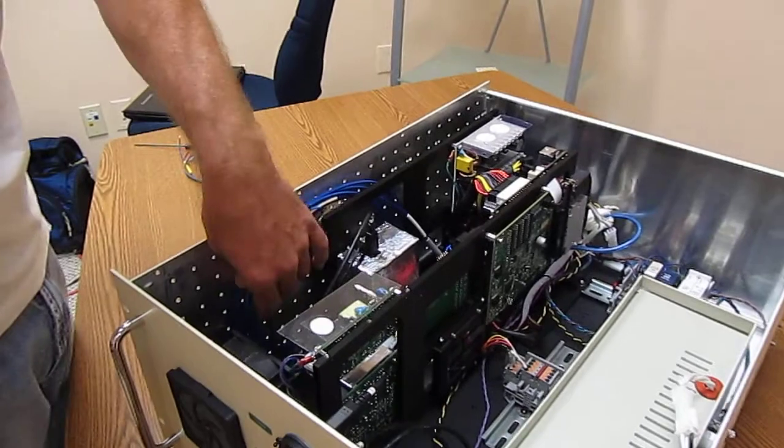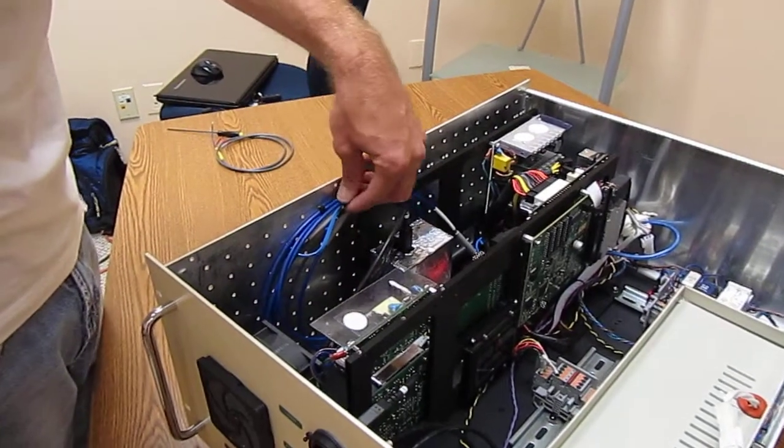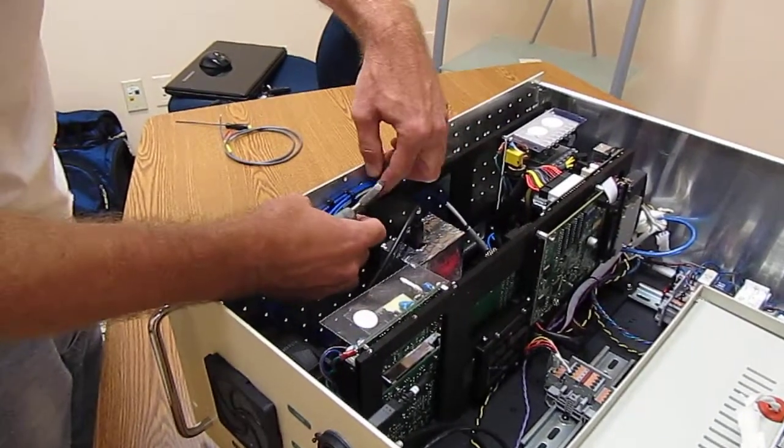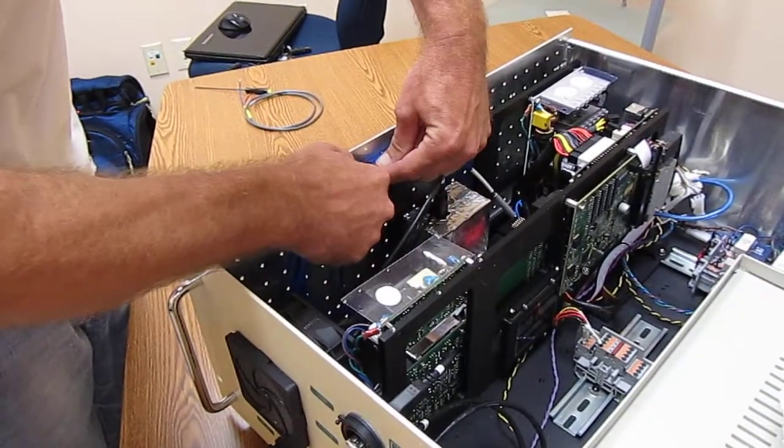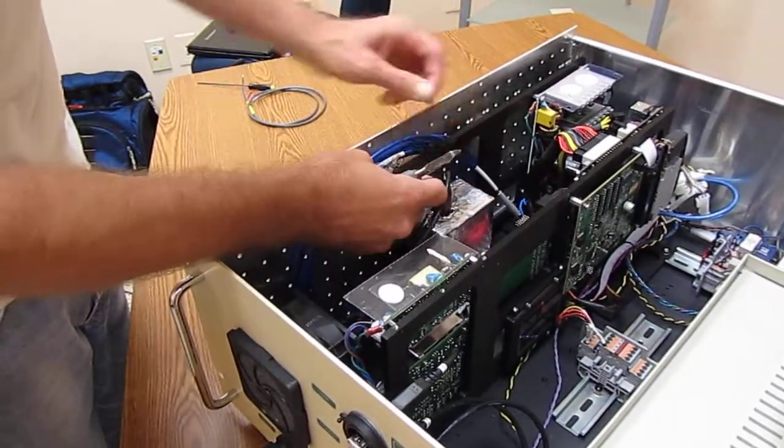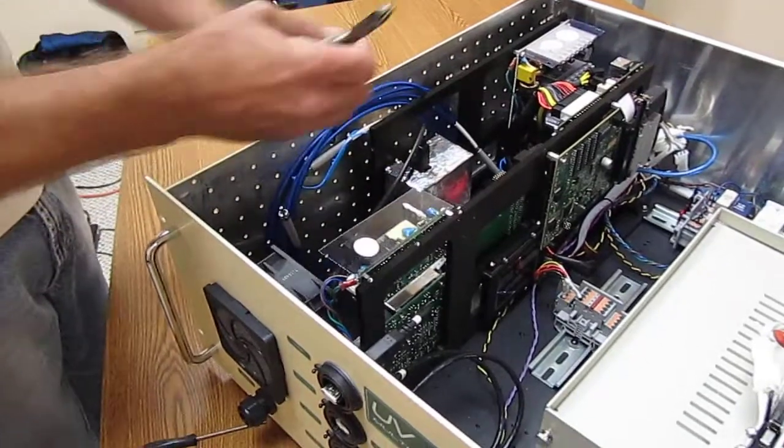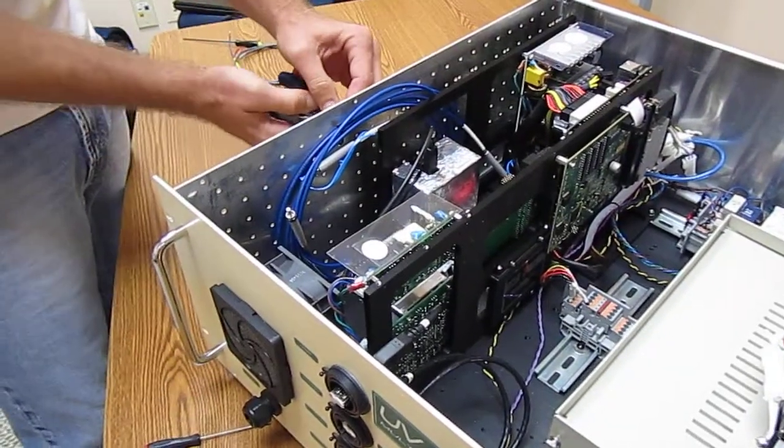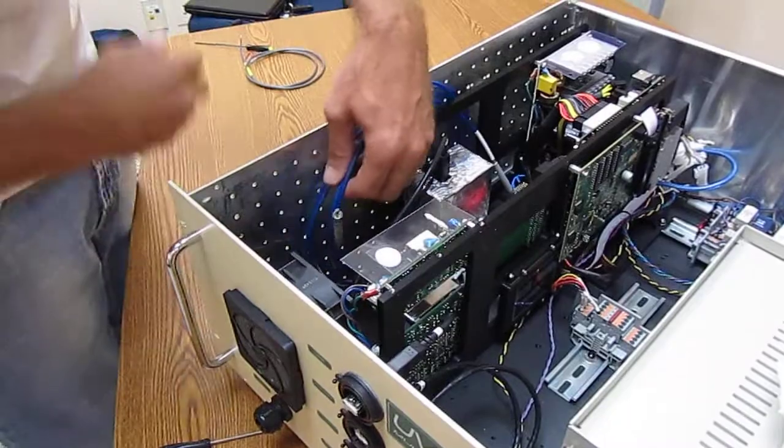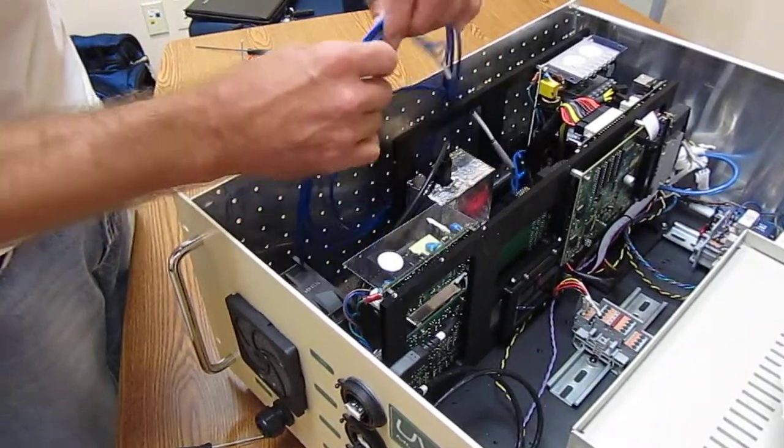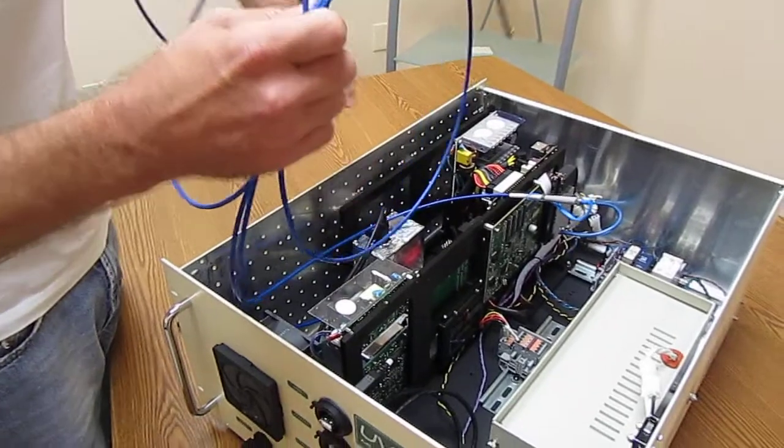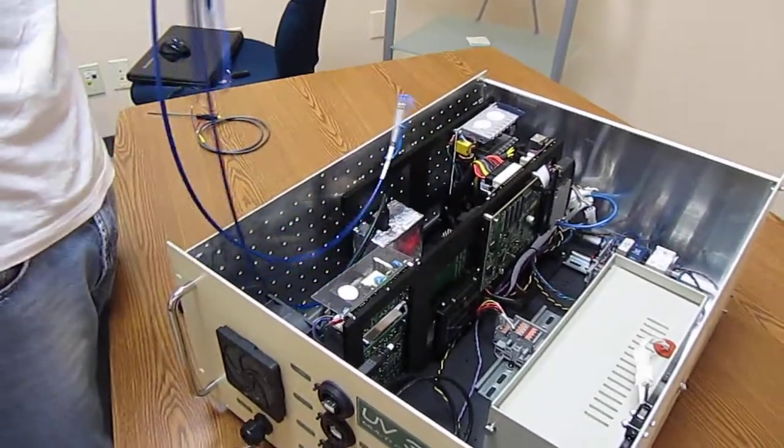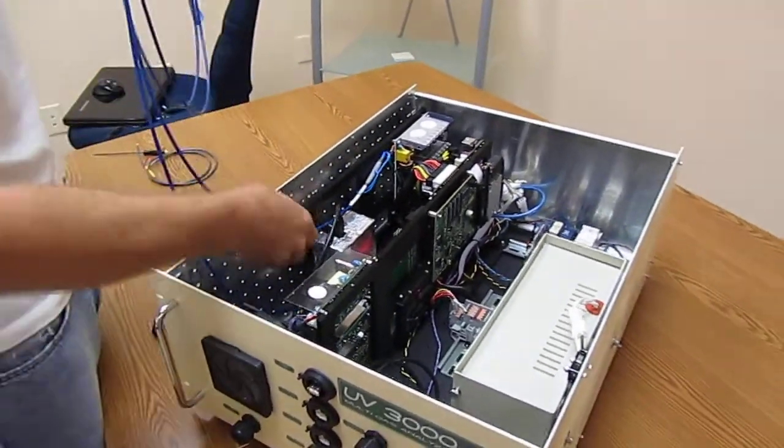Alright, this procedure will demonstrate setting up the UV-3000. Snip the zip ties that hold the fiber optic cables. Gently remove the cables and never bend them sharply.